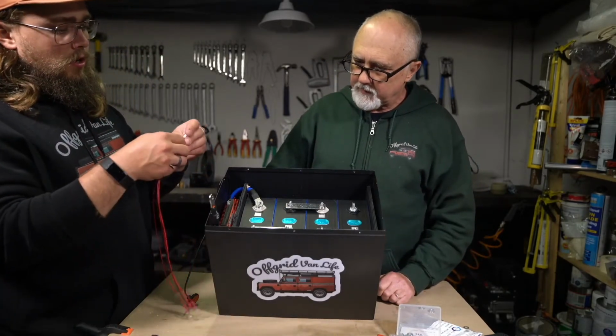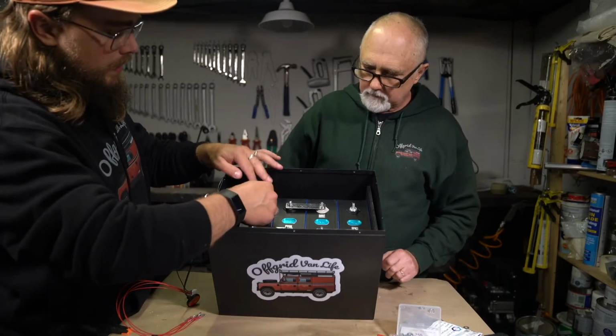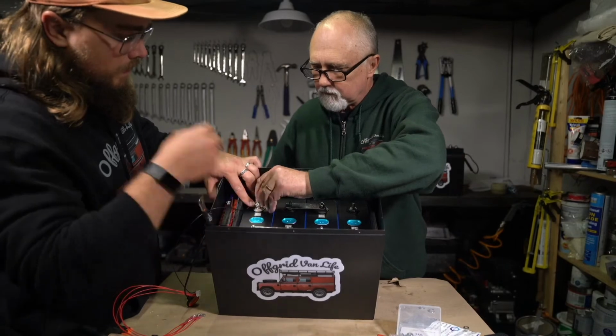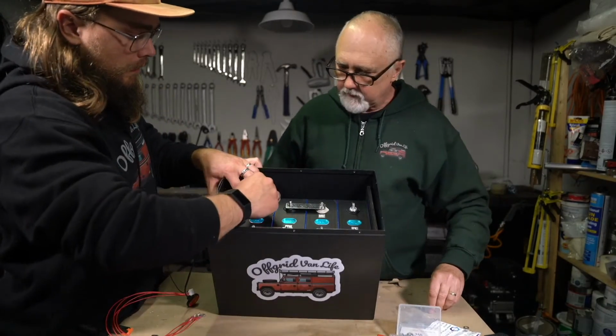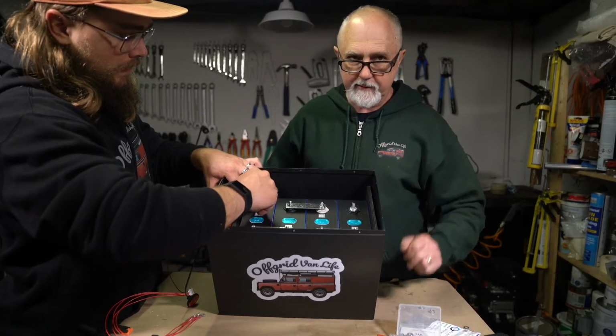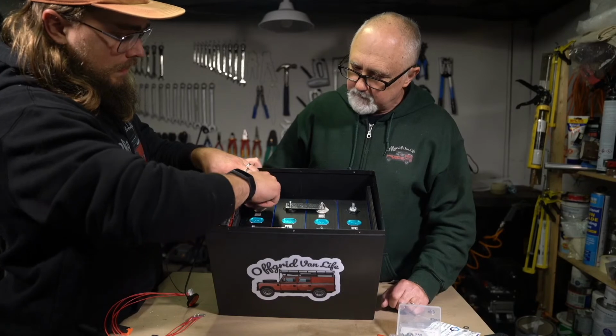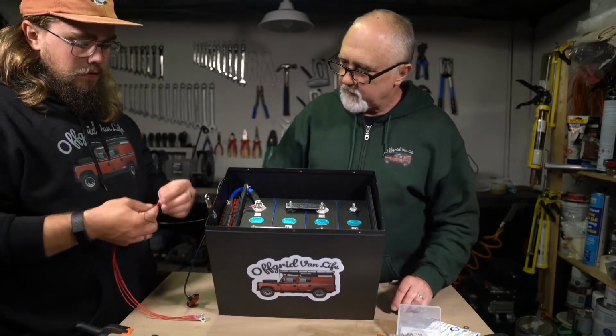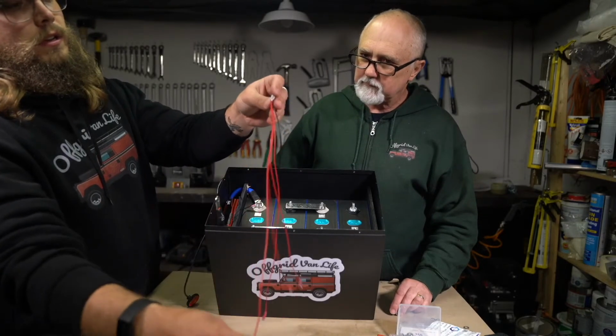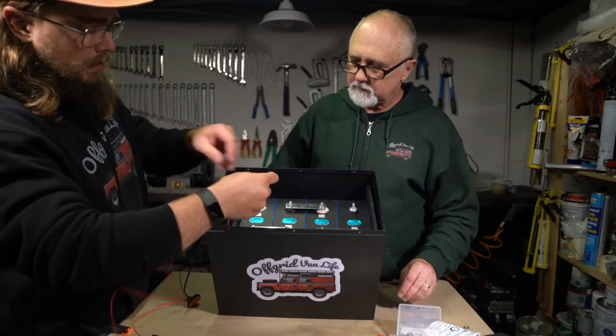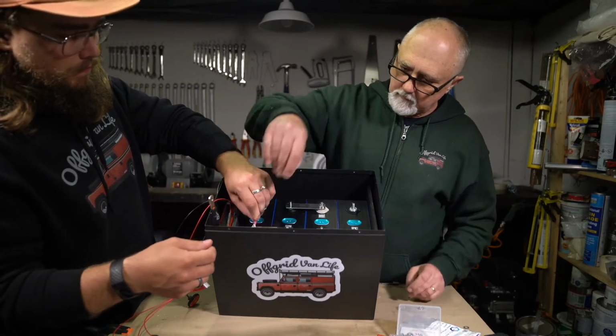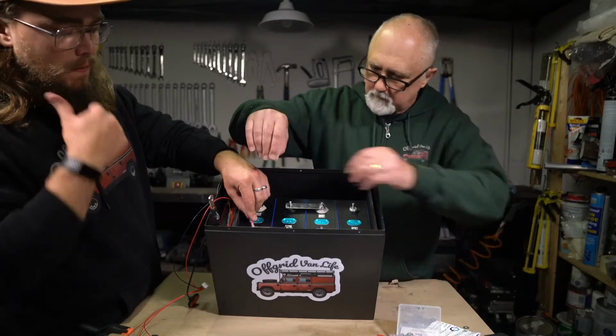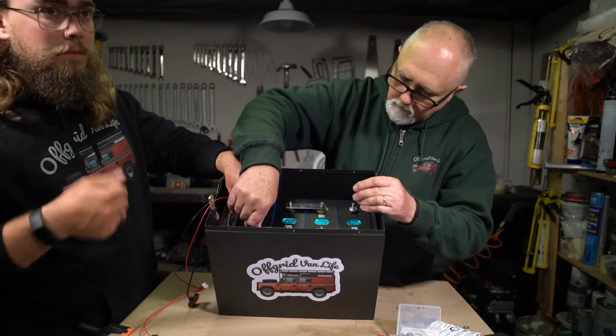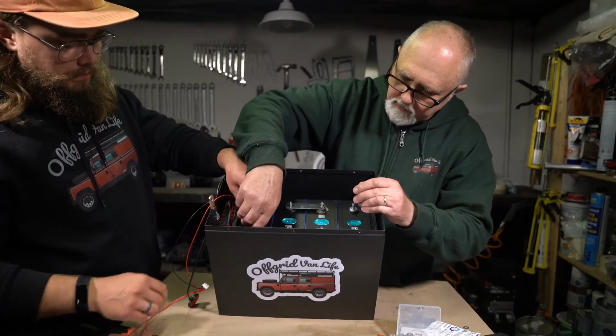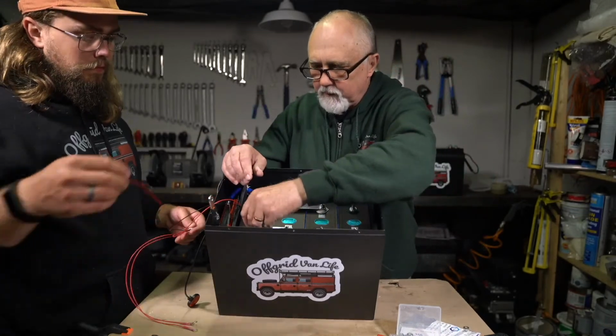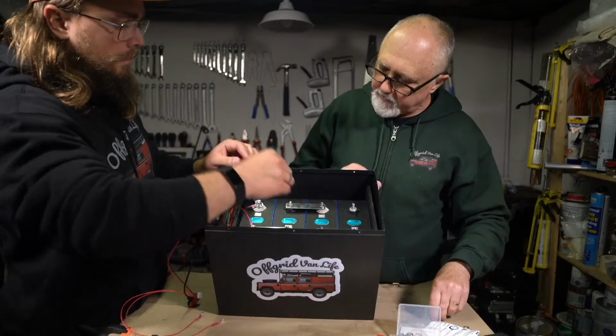These all go in sequence, so we start with the negative, which goes on there. Try very hard not to drop the nuts, because if they fall in there, you never get them out. Then the first positive - we always go in the right order from the plug, to make sure we get them in sequence. We always put a little washer on, because when the nuts tighten, they twist the leads around if you don't use a washer.